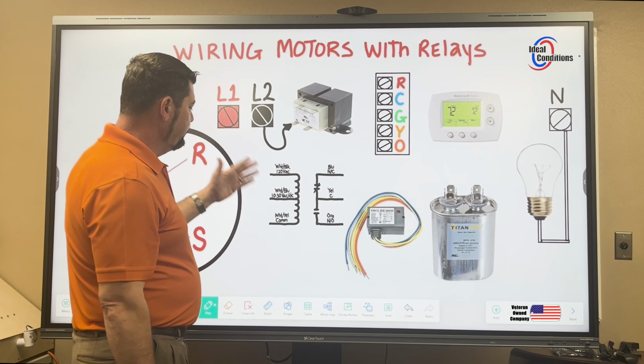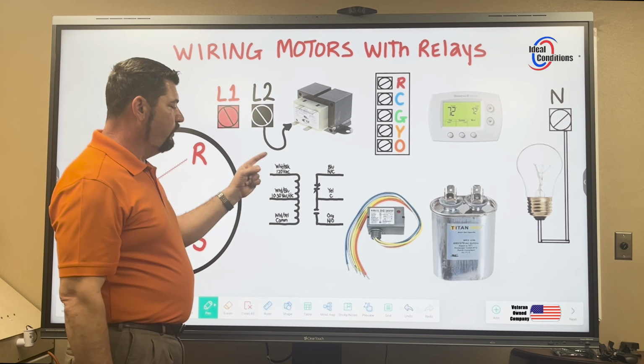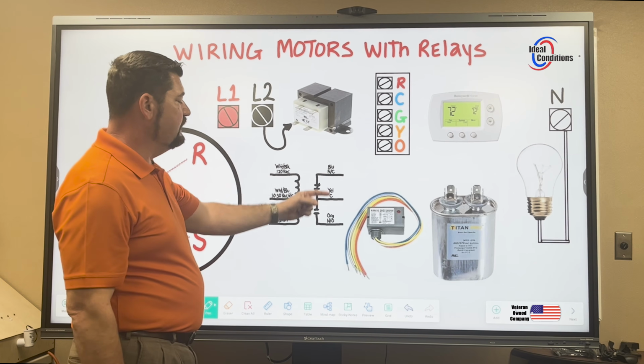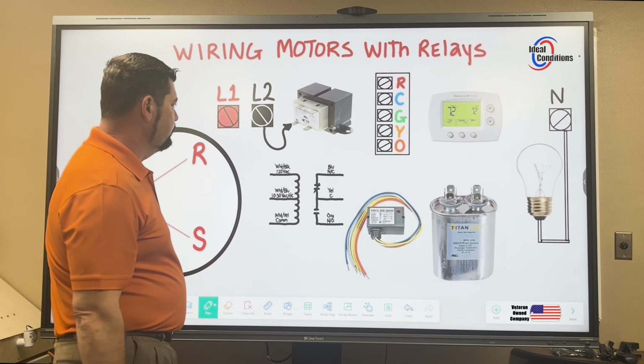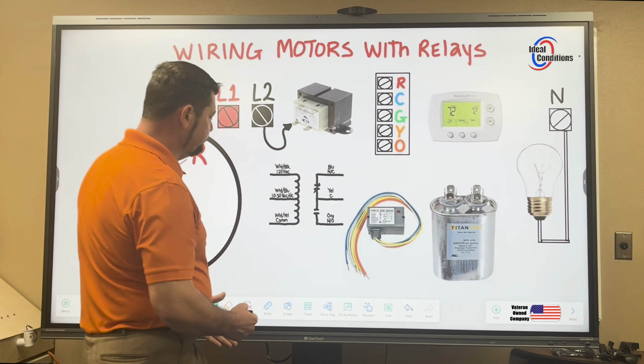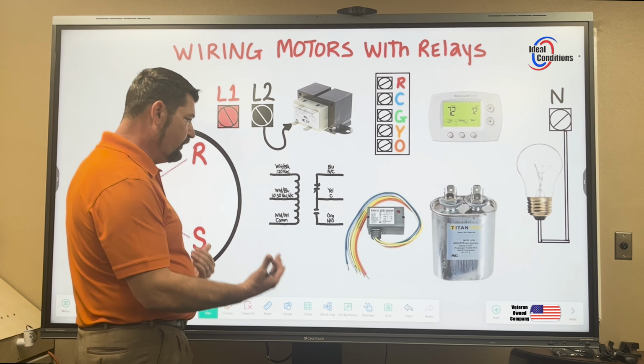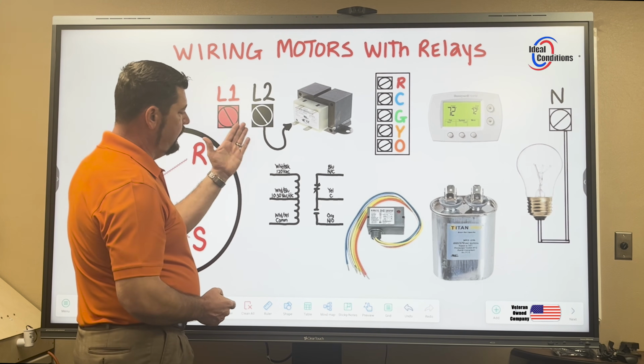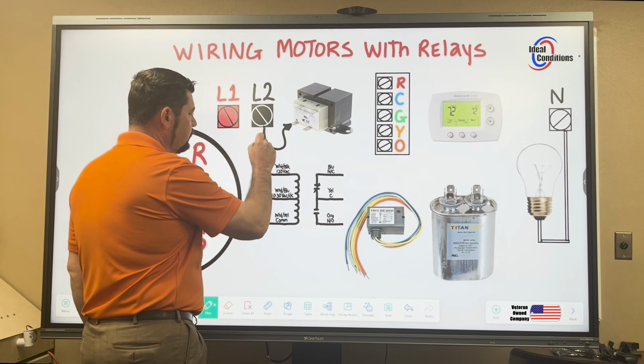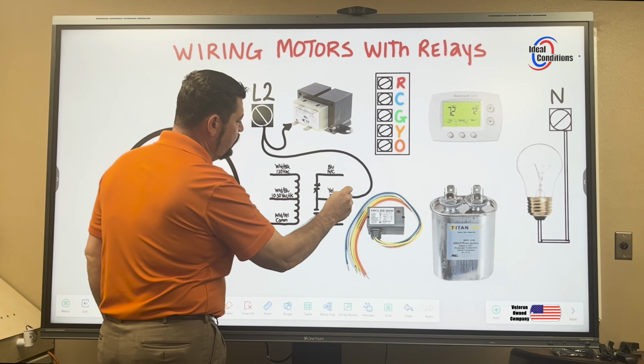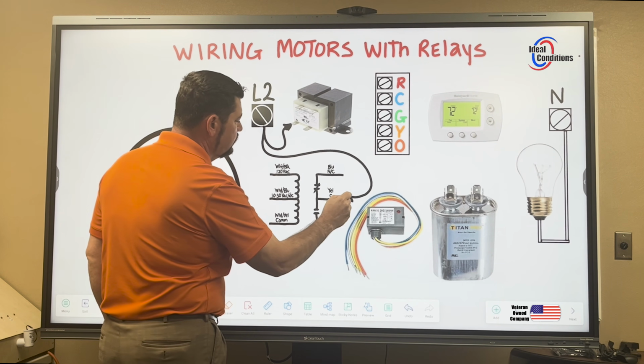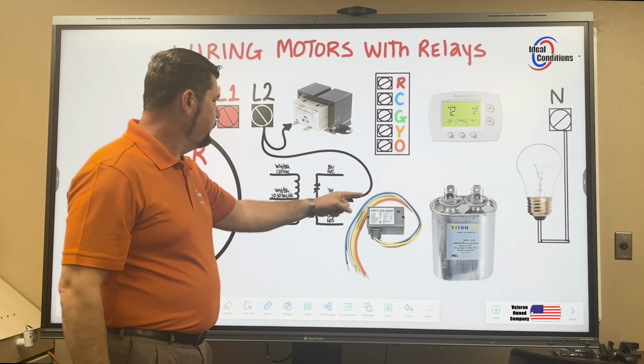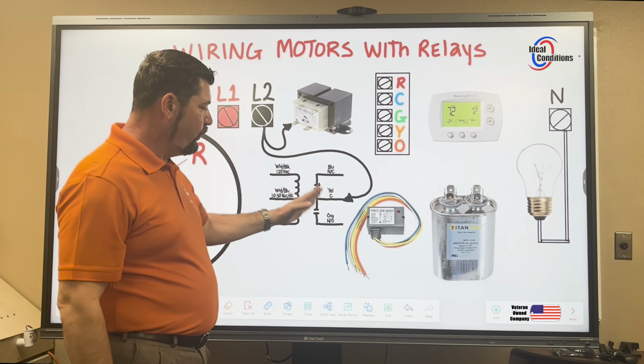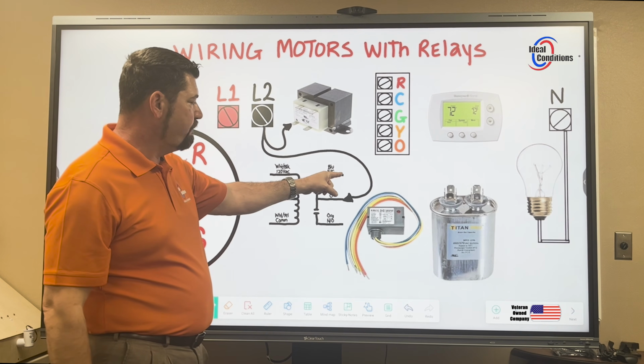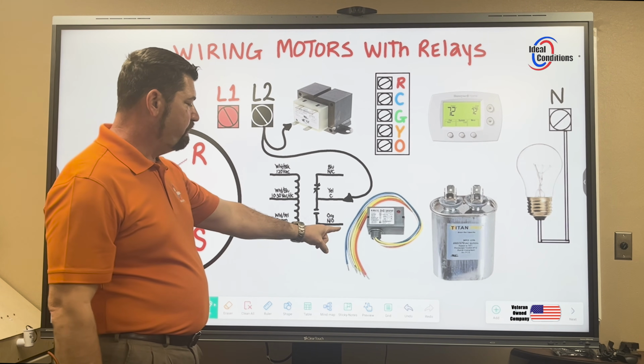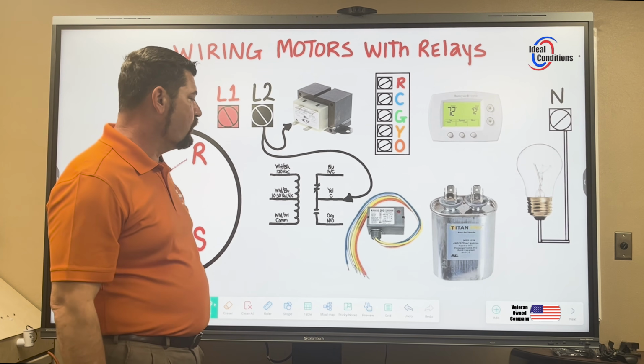So I'm only going to wire 2 out of these 3 coil voltages, and I'm going to wire both of the output contact voltages. We're going to come down first and wire this up traditionally. So L2 next will come over, and I'm going to come over to common, which is my yellow wire. All right, and I'm going to input one leg of power. At this point in time, I now have power right here. I don't have power here yet, but I have power here already.